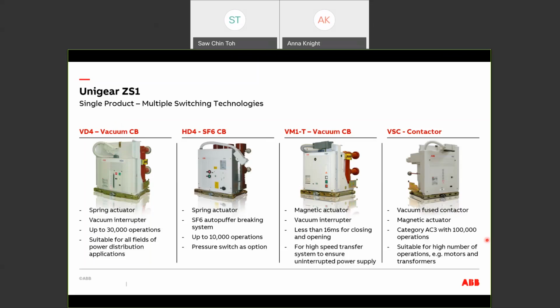Other than vacuum circuit breakers, ABB also offers SF6 circuit breakers type HD4. The vacuum circuit breakers and the SF6 circuit breakers have pretty much similar ratings, and depending on the customer preference, we can provide accordingly. For applications where high-speed transfer is required, we have VM1 vacuum circuit breakers. Different from VD4 and HD4, this type of circuit breaker uses a magnetic actuator, and the closing time and opening time is less than 16 milliseconds. With such high-speed switching, we make sure that there is no interruption to the power supply.